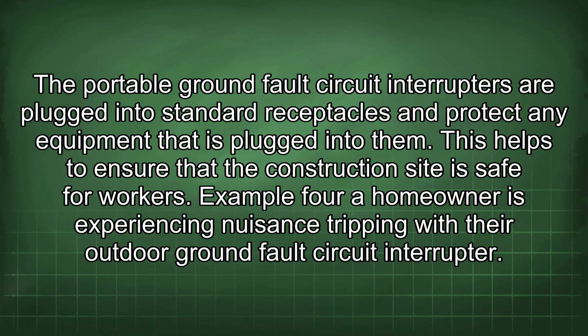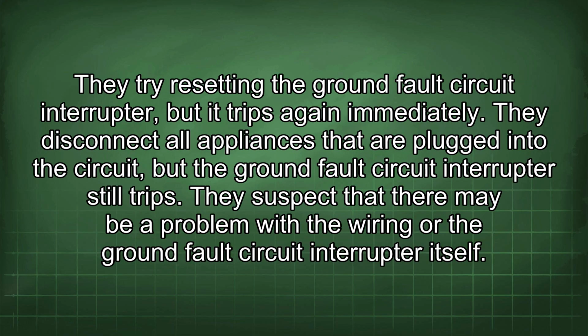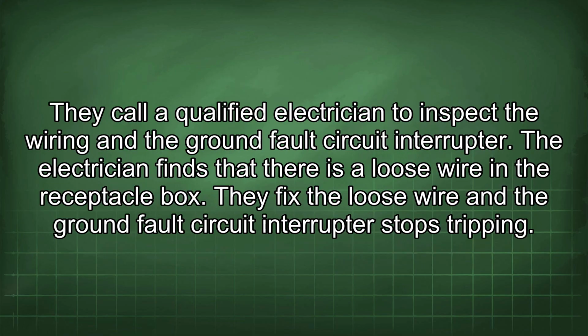Example 4. A homeowner is experiencing nuisance tripping with their outdoor ground fault circuit interrupter. They try resetting the ground fault circuit interrupter, but it trips again immediately. They disconnect all appliances that are plugged into the circuit, but the ground fault circuit interrupter still trips. They suspect that there may be a problem with the wiring or the ground fault circuit interrupter itself. They call a qualified electrician to inspect the wiring and the ground fault circuit interrupter. The electrician finds that there is a loose wire in the receptacle box. They fix the loose wire and the ground fault circuit interrupter stops tripping.